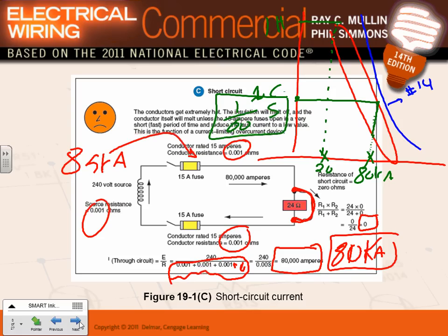Do you guys see the gravity? Everybody can see the gravity, okay? Let's take another overload condition. Suppose that you have 100 amps. You're pulling 100 amps out of it. Come over here. Here's my time. Let's just say 1 minute. Took you 1 minute. All these graphs, guys, are coming from the manufacturer. I'm throwing numbers here, but these graphs for the fuses are coming from the manufacturers.